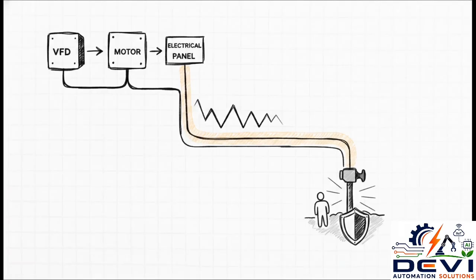Let's talk about earthing, or grounding. Now, in a VFD system, this actually serves a pretty brilliant dual purpose. First, it ensures strict electrical safety. By properly earthing the VFD, the motor, and the panel, you're protecting personnel from lethal electrical shocks. But simultaneously, it acts as a shield ground.